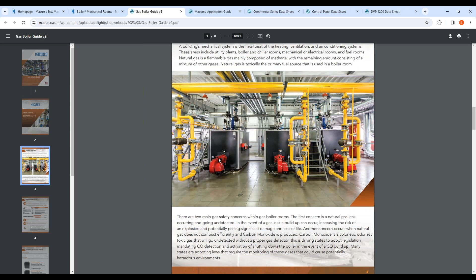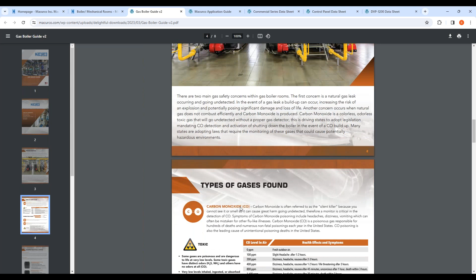So I'm going to backtrack real quick, and we're going to educate specifically on this application. I'm going to go into the boiler room application guide real quick. To give you a reference point, a lot of the states that have this boiler code, we've put into play just from a collateral standpoint, and we've transitioned that into an overall boiler guide. In a boiler room, you have a combustible gas: methane, propane, natural gas. For those that aren't familiar, methane and natural gas are semi one and the same. But the one thing you have to concern yourself with is that anytime you have carbon monoxide, it's coming from a combustible gas. So carbon monoxide is the code-driven formula here. As you can see on page 3, we have the types of gases found, which is combustible and carbon monoxide. It gives a breakdown of the goods, the bads, the uglies.